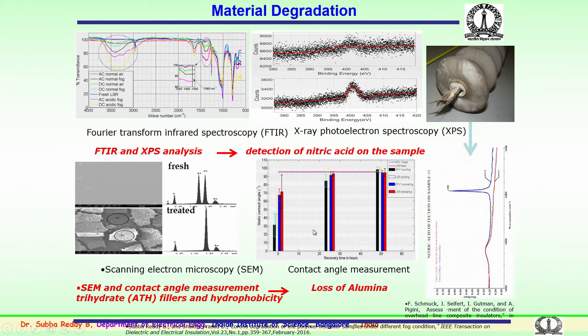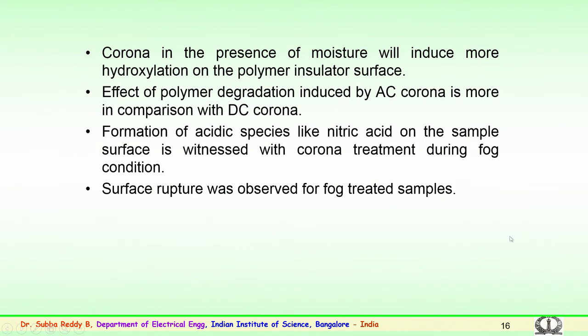There is a standard for the hydrophobicity measurements. The performance is verified and it is being estimated. So, this is a very important aspect for the detection of the hydrophobicity effect and how the performance of the hydrophobicity changes. So, we have seen that corona in the presence of moisture will induce more hydroxylation on the polymer insulator surface. Very important point.